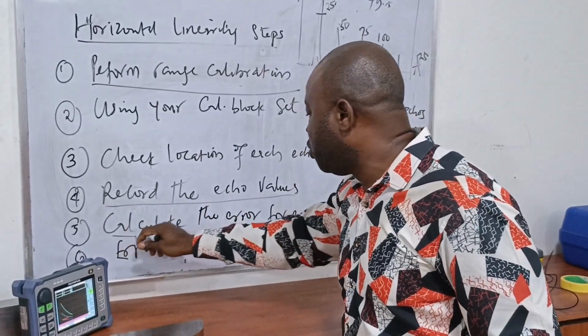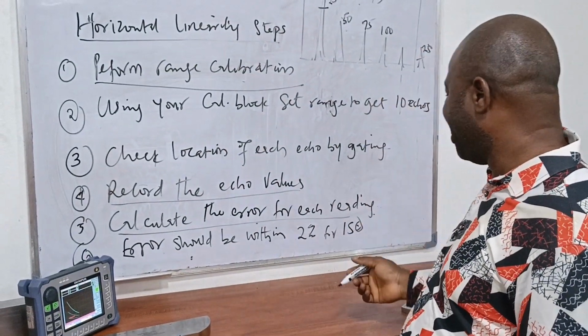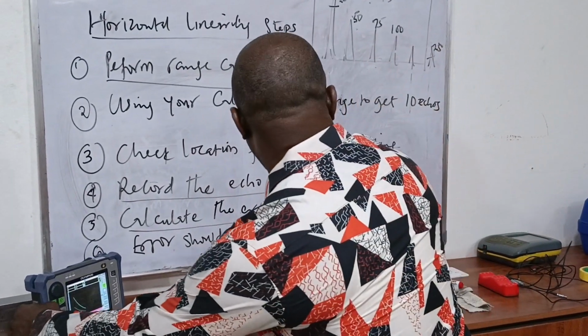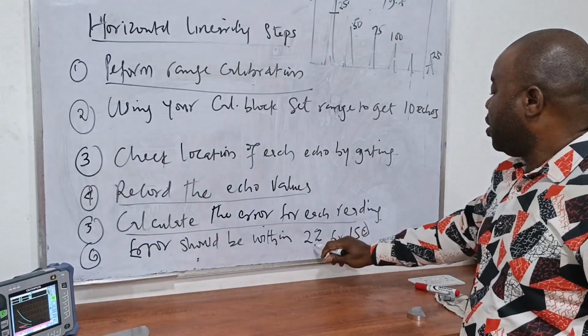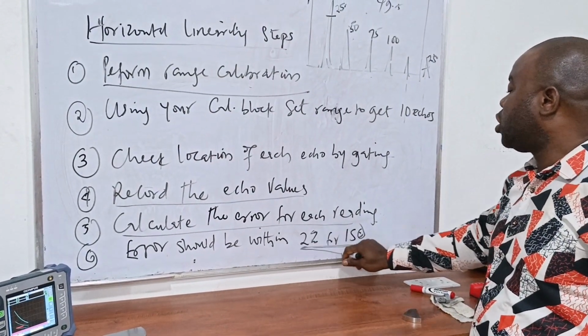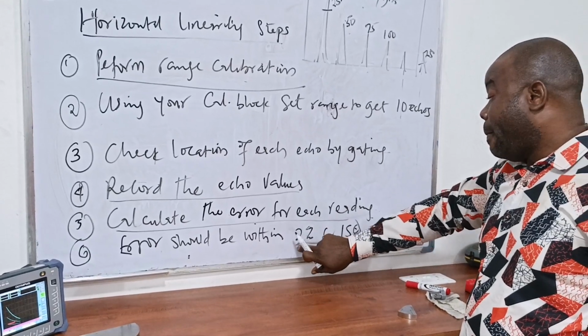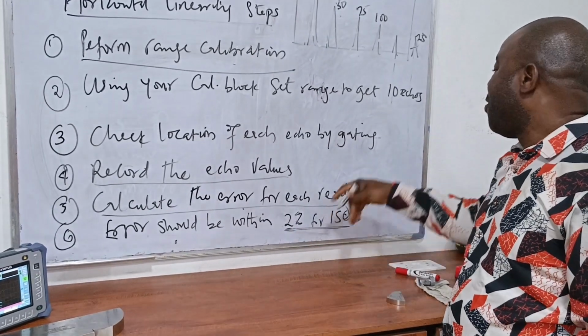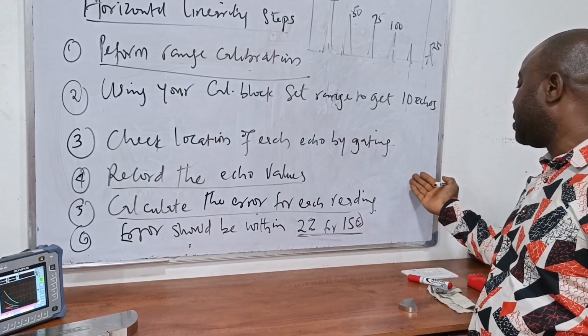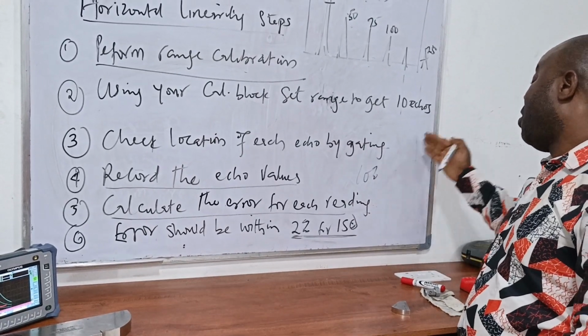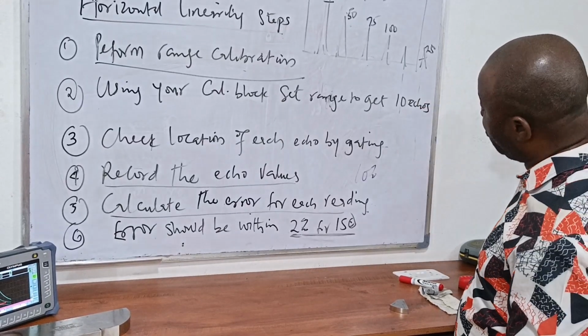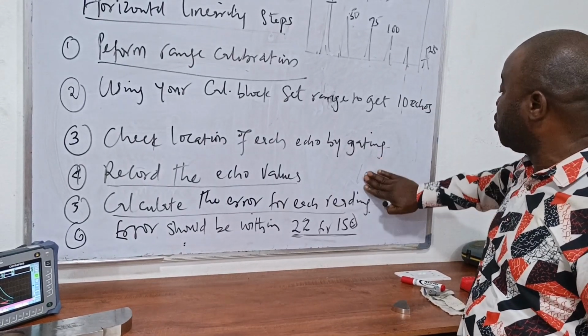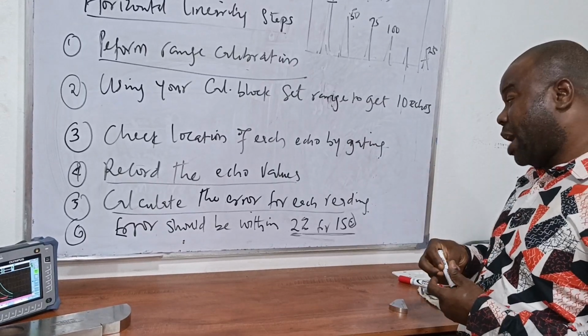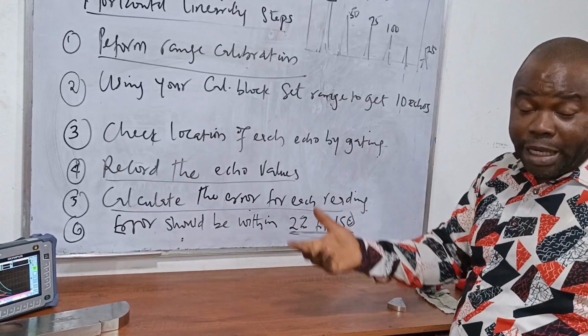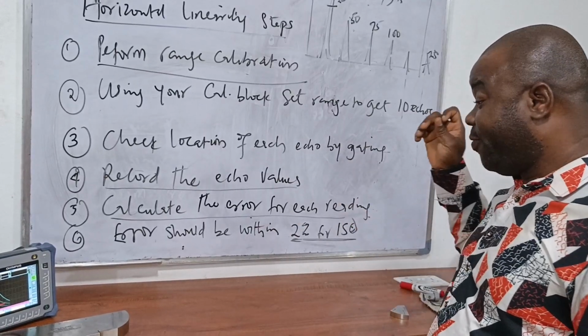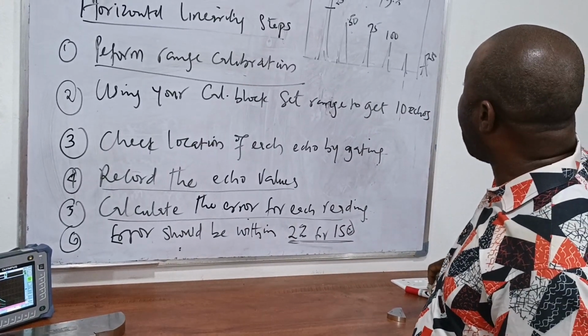Then the next step is to calculate the error for each reading. For ISO, the requirement is that your error should not be more than 2%. For ASME, it is a different requirement. ASME is 10% of your reading or 5% of your range. You can check that out. I will not go deep into that for now, but most times we normally use the ISO. Depending on the project you are involved in, you need to be very sure what your error requirement is.